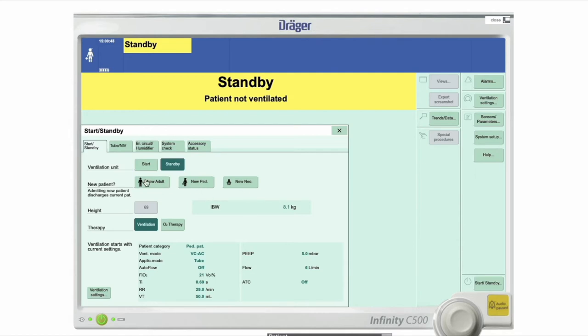For adults and children, this flow is sensed once it's gone back to the expiratory limb, back into the ventilator. But because the volumes that the neonates generate are so small, that sensor has to be placed as close to the ET tube as possible. So there's a sensor that needs to go on the end anytime you put the patient in neonatal mode. The other difference between them is that if you select neonates, wait for it to sort itself out, you have to put in the ideal body weight, and you put that in here.